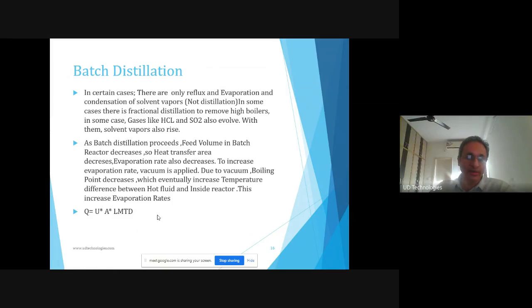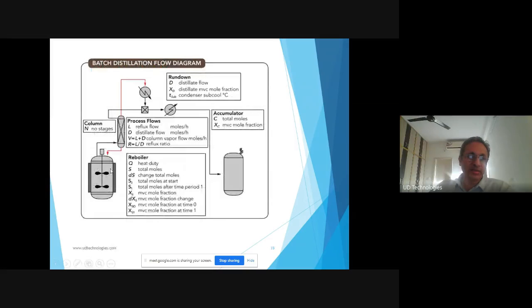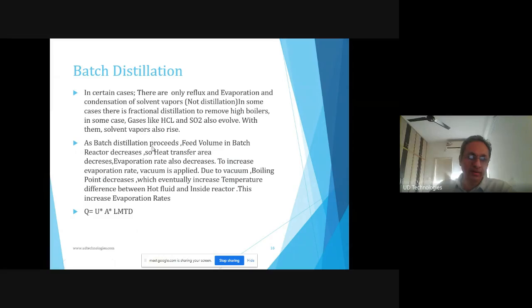So because of this, vacuum is applied. Once the reactor is completely filled up to the top, when vapor is increasing and solvent is recovered in the receiver, the volume will go lower and lower, and so will the heat transfer area. What is the heat transfer area in a cylindrical reactor? It is only pi dl. As the length or height is decreasing, your heat transfer area is also decreasing. At that time, your evaporation rate will also decrease. So these are the fundamentals of why vacuum is applied.